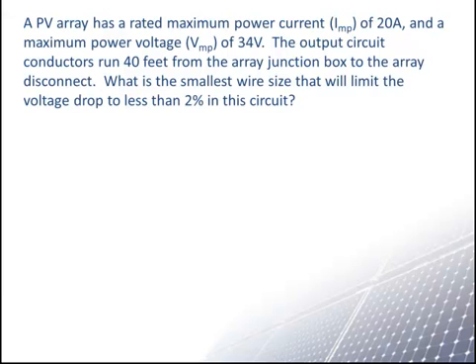The first thing that we need to do is determine the allowable voltage drop. Multiply 34 volts by 2% for an allowable drop of 0.68 volts.